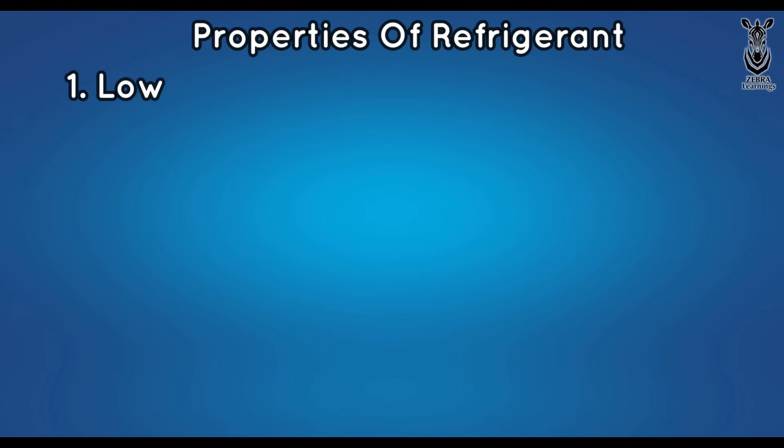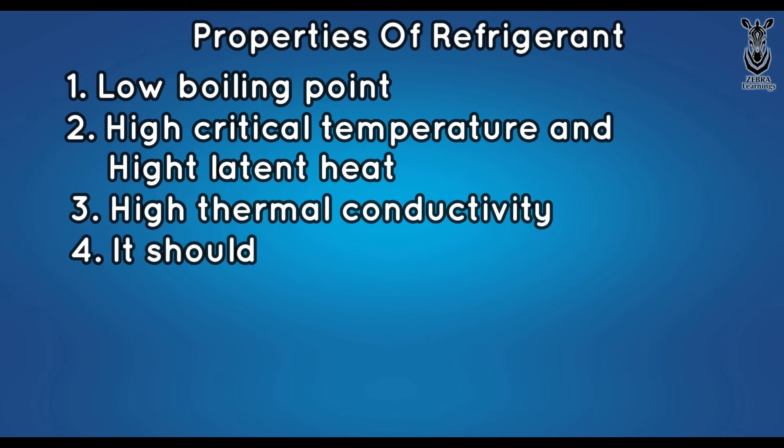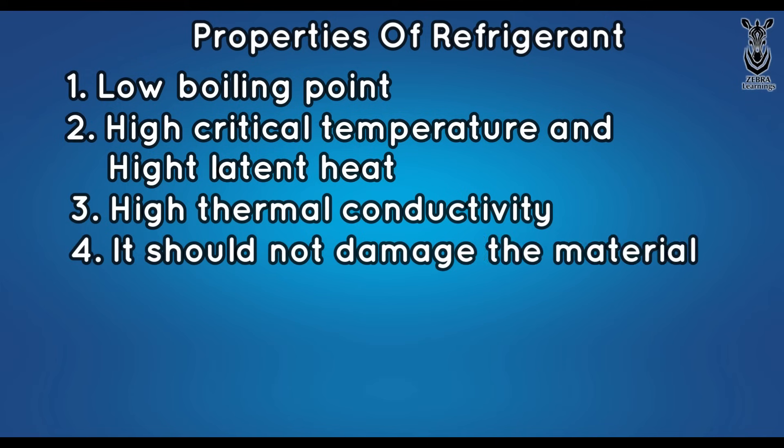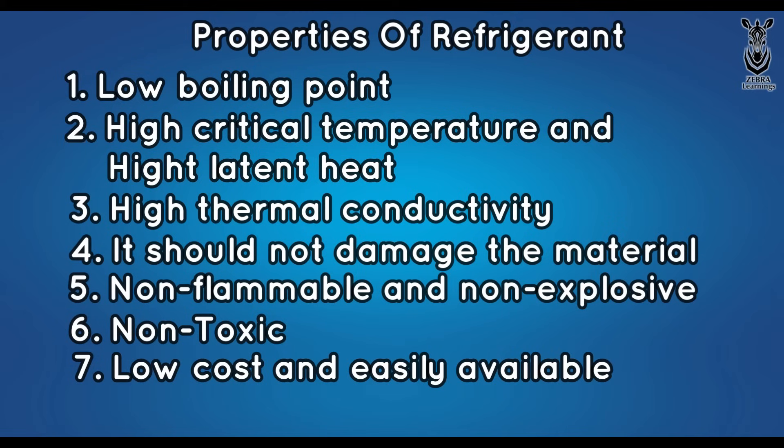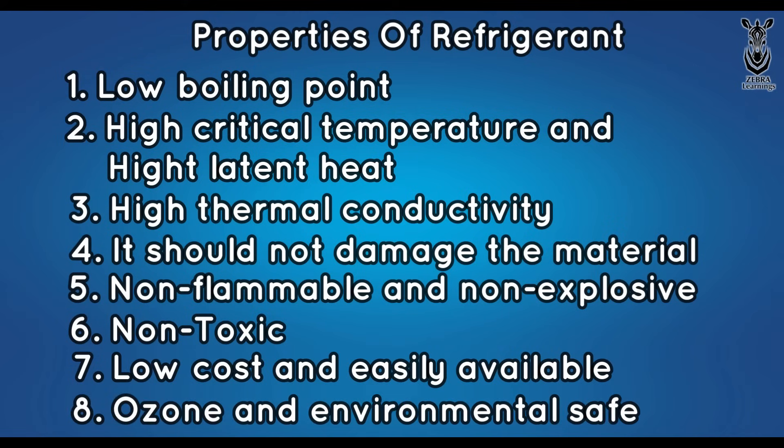A refrigerant must have certain properties. Its important properties are: Boiling point should be low. There should be high critical temperature and high latent heat. There should be high thermal conductivity. Should not cause any harm to the materials. Must not be flammable or explosive. Should not be poisonous. Should be cheap and readily available. There should be no harm to ozone layer and the environment.